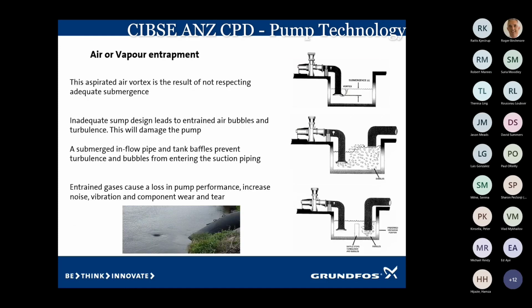Other places where we can get air, we're pulling water out of a stream, a cooling tower. If that water level is less than 500 mil, then you can pull a vortex from the surface. So you'll get air pulling down off the surface, like pulling the plug out of the bath, and it'll draw it into the intake of the pump, and it'll cause the pump to starve, and eventually it'll stop pumping. We can get the second diagram down. You can see here's a lot of aerated water coming in here, and that's going straight into the pump.